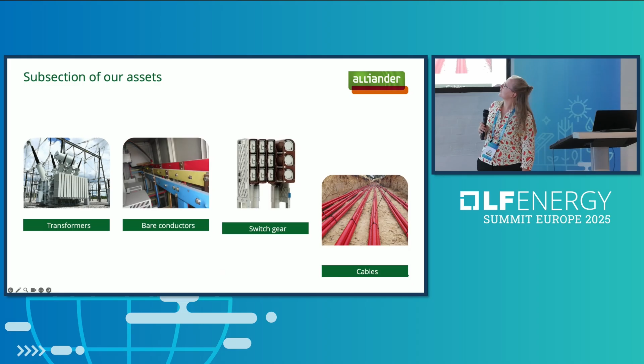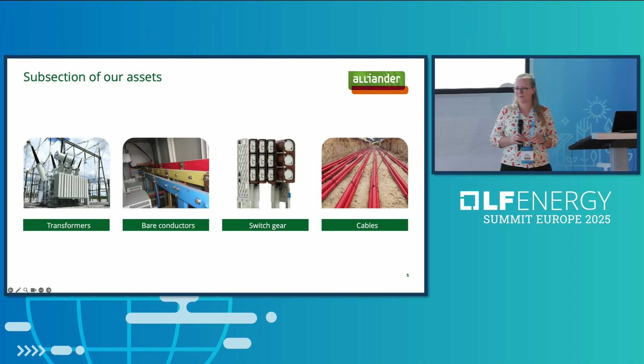As we increase the load of these assets, we'd expect them to be quite warm, since the map is red, so we'd expect these assets to approach their thermal limit. But if you look at these assets again, for example the oil of one of our transformers in a distribution grid, we see they're not that warm. These temperatures are allowed to rise above 100 degrees Celsius, yet most of the time these transformers aren't that warm yet. So it seems many grids have some thermal residual capacity left that we can use as well, and that's what we're working on.